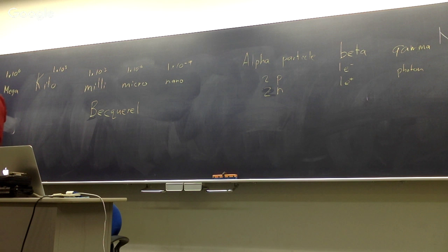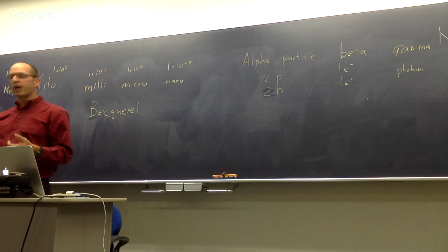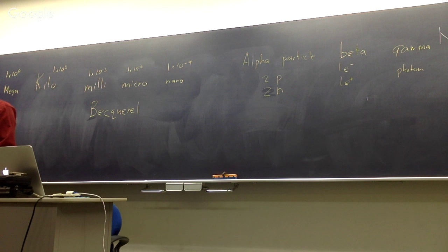And in most of the reactors that we use for power generation, we use a water moderator. So the water that's surrounding the fuel rods has a number of purposes. It cools the reactor, it brings the energy actually out because we can circulate it through to make steam and turn the turbines, but it also is a part of the nuclear reaction in that it slows down the neutron in order to enhance the likelihood of a reaction.